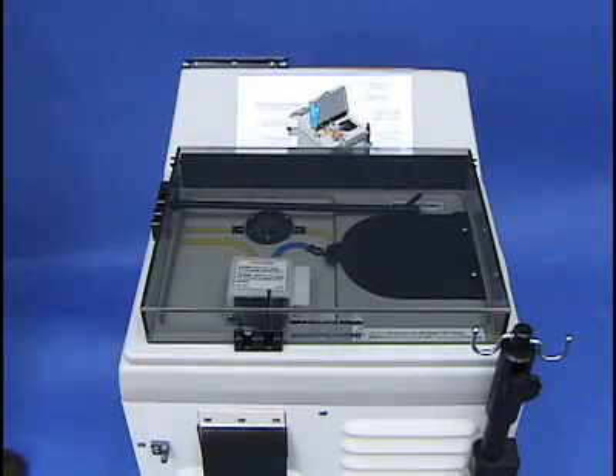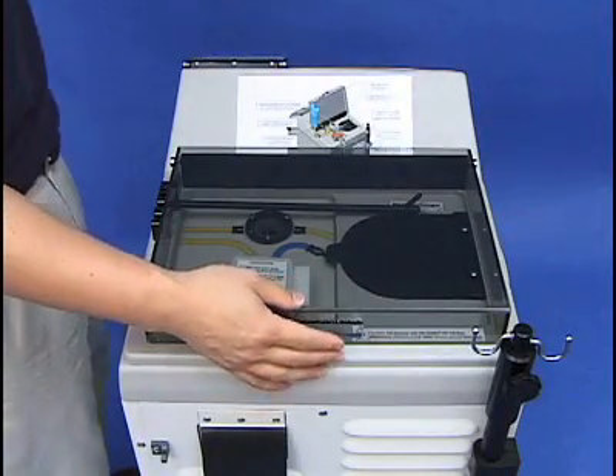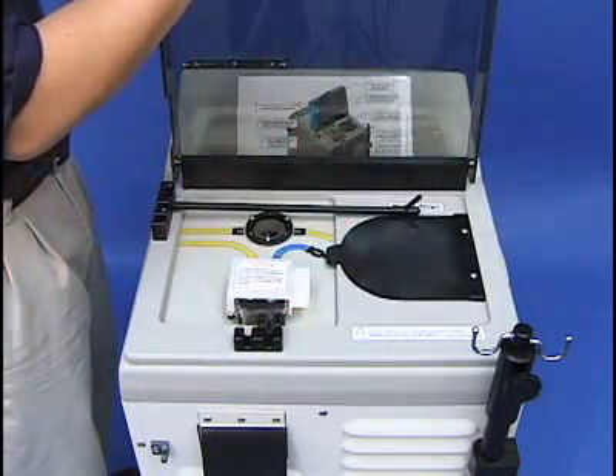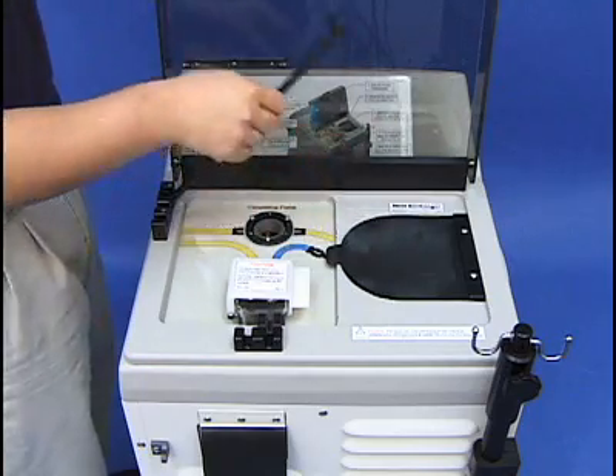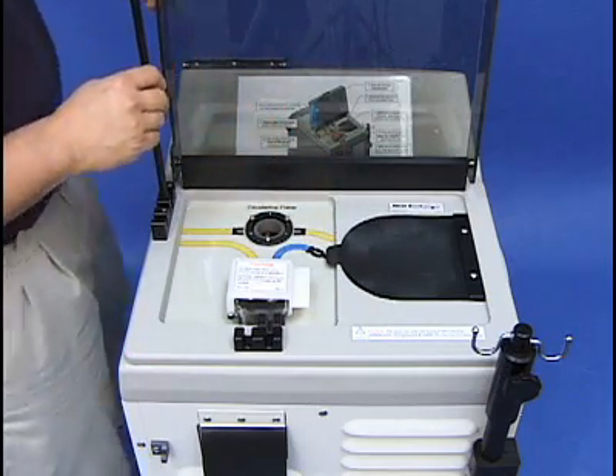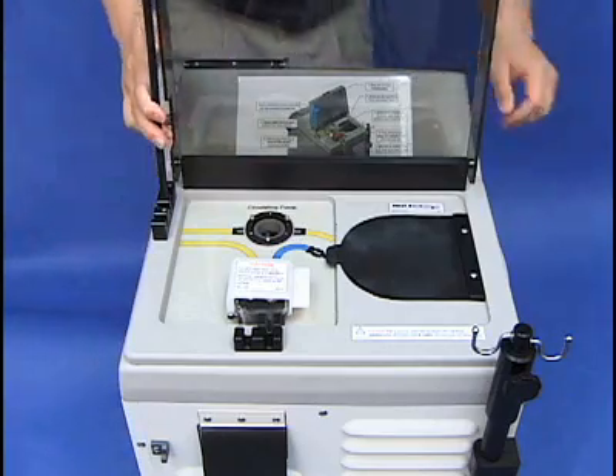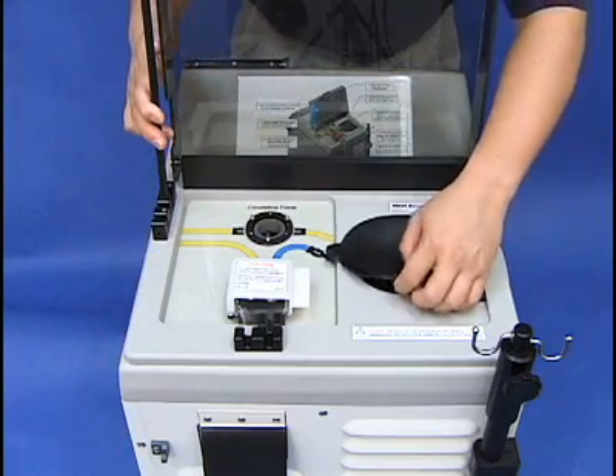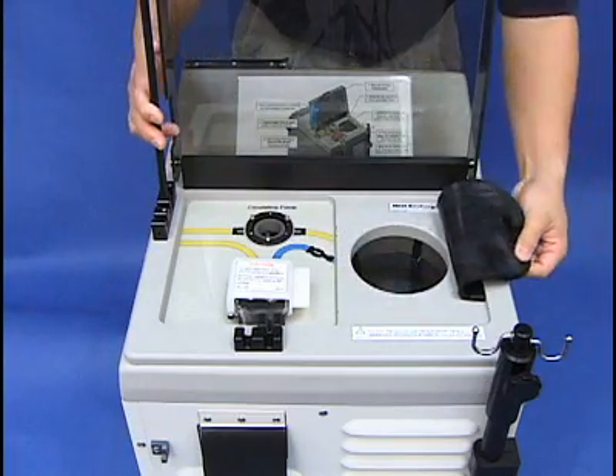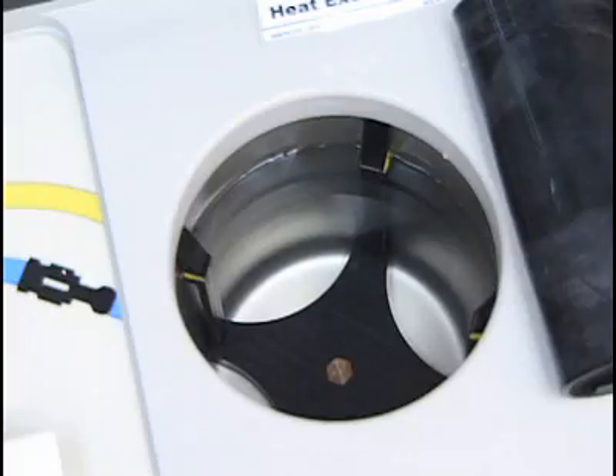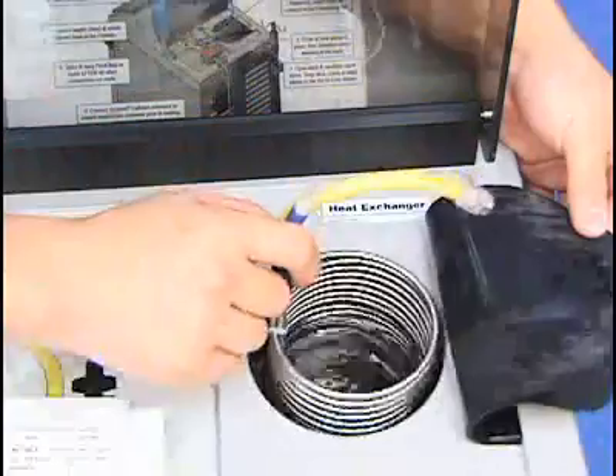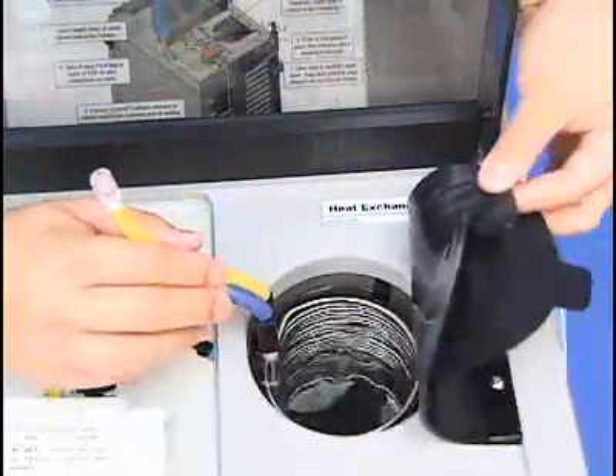Then go to the back of the console, lift the lid, lift the bag stand out of the way, and then check to see if the bath level is up to the yellow fill lines. If this were not full, this would be the time to top it off. Then place the heat exchanger in the bath with the connectors facing in the direction shown on the installation diagram.